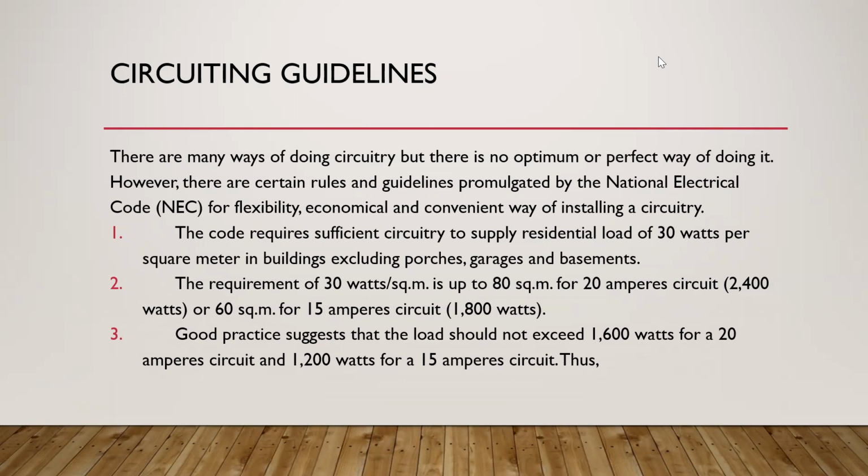The good practice suggests that the load should not exceed 1,600 watts for 20 ampere circuit and 1,200 watts for 15 ampere circuits. So kumbaga, dun sa ating 20 amperes which is converted to 2,400 watts, kumbaga yung computed electrical load should not exceed 1,600.